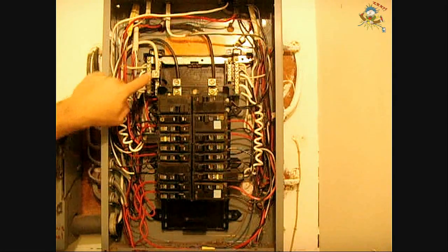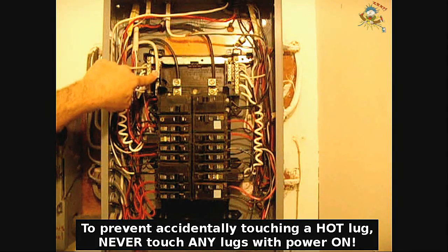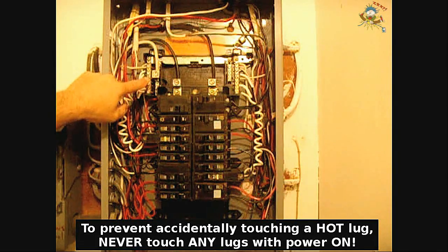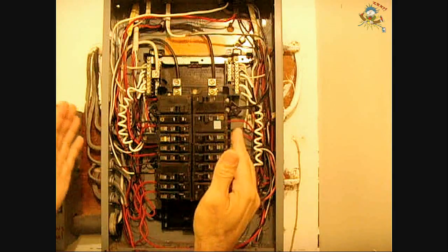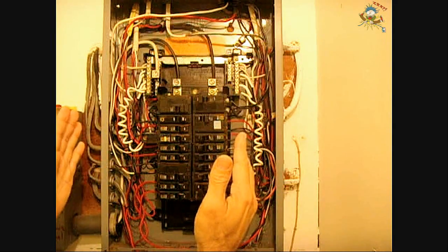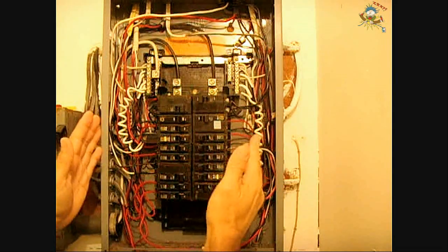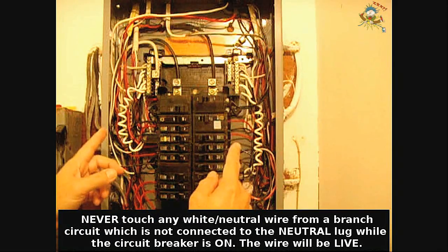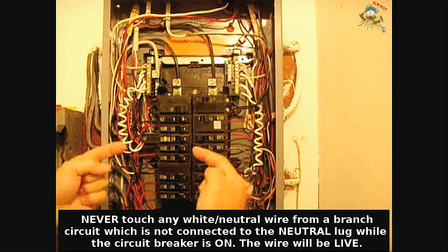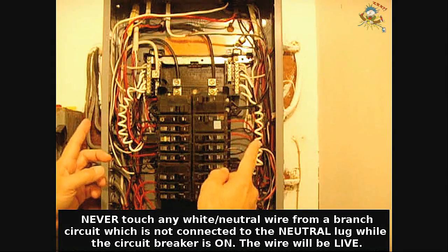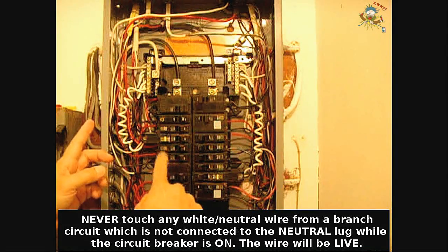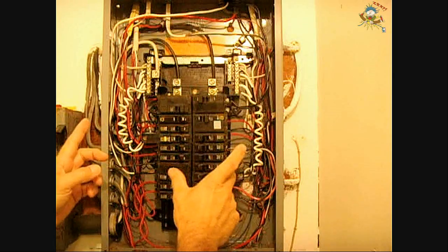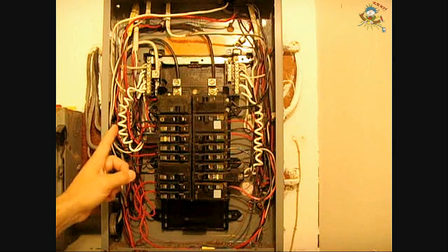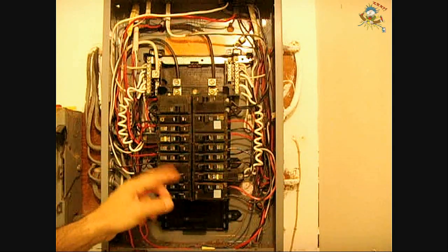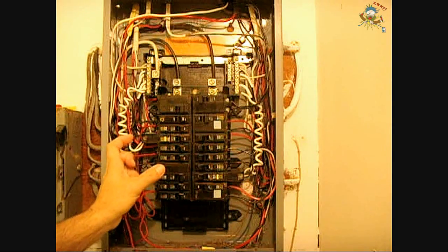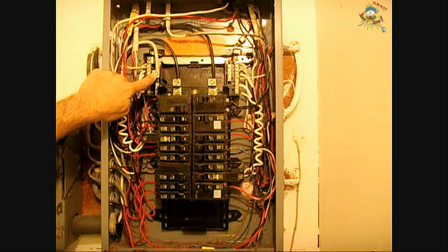Now the neutral wire, which is right here, you could touch that one, believe it or not. All right, power on. This is connected to the ground. On the utility pole, on the transformer, or on your pad mounted transformer, you have your 3 terminals. The 2 outer ones are 120 volts each. The 2 together make 240. From the outer connection to the center would be the 0 volt connection, which is the neutral. That's 120 volts. And the outer connection on the transformer to the inner on the left side, you would also have 120. So this is 0 volts potential.